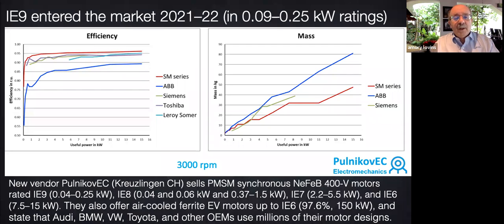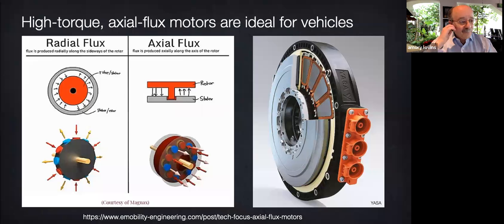Well, then again, only the EU and Switzerland and UK have adopted IE4 as the standard for most industrial motors. The IEC hasn't declared any higher standards. China's standard for motors above 3/4 of a kilowatt were raised to IE3 only in 2021. India's voluntary standard for all motors remains IE2. Many older motors are much worse than IE2 or even IE1. So for most of the world's motors, there's a long way to go to get into these rarefied efficiency ranges.